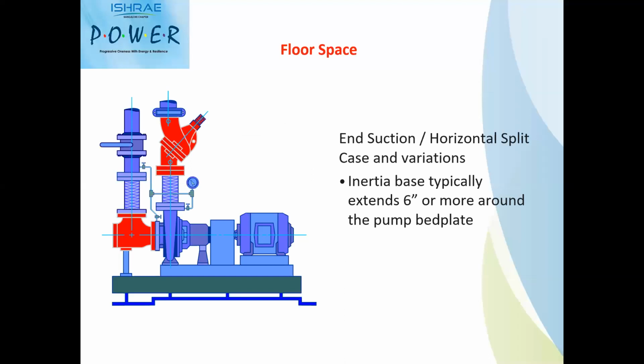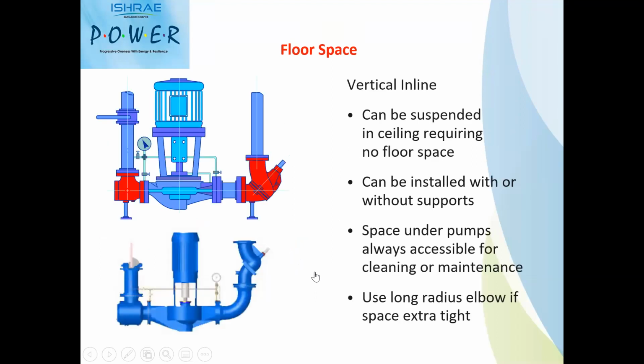Whenever you come to end suction pumps, a typical end suction pump has to have a base plate. It has to have a foundation. Since these are all long coupled, flexible coupling designs, there will be vibration from these pumps, so you need to have flexible bellows for the pumps. So any end suction pump, when you want to install it, you need a minimum of these components. And floor space wise, since it is a horizontal design, it requires bigger floor space compared to vertical inline pumps.